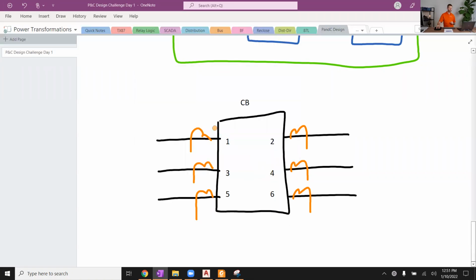There's a convention to this. The primary polarity dot on the outside of the bushing, and then the secondary. Primary, secondary, primary, secondary. But on the other side of the breaker, your primary polarity dots, again, are going to be on the outside of the bushing, which is the opposite direction from the flip side. Why do we do that?